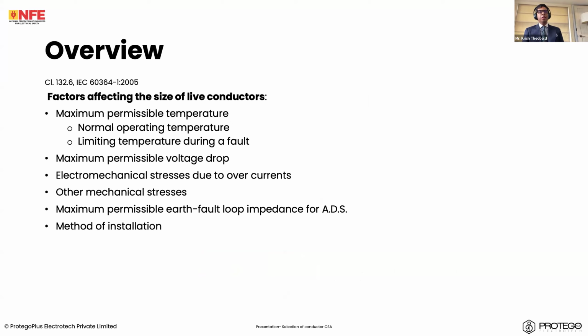When we select the size of cables that we use for our live conductors, there are a variety of factors that we have to take into account. The most common one that we talk about is temperature, and that's directly related to the current carrying capacity. Normal operating temperature is the temperature the cable's insulation can handle without being permanently damaged, particularly at steady state. Then we have limiting temperatures, which is, during a fault, what's the temperature of the cable? Again, of the insulation. Voltage drop, how much voltage drop can we possibly allow?